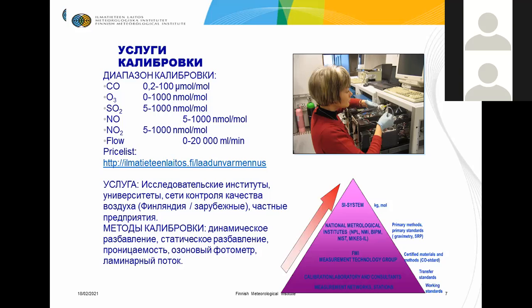And of course, the transfer standard has to be calibrated against the certified materials in the calibration laboratory, the National Reference Laboratory in FMI, because they have the higher standard in the calibration laboratory, and those are the certified materials. They have the certified materials, and that's also more pricey. So it's not economical that all of these 150 stations would have the certified materials in each of the stations, because it would cost an enormous amount of money. That's why we have these highest certified materials only in one place in Finland, and that's the National Reference Laboratory.